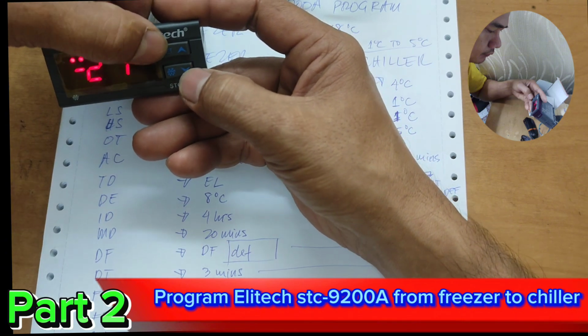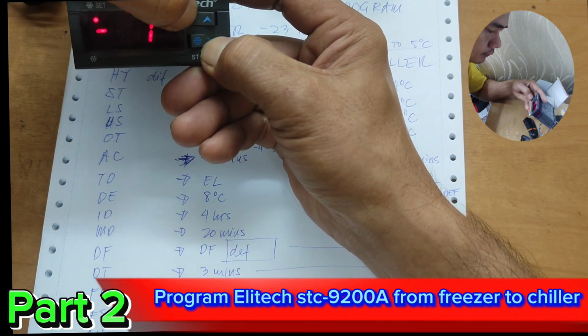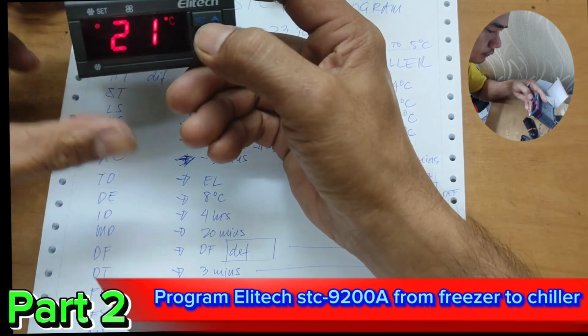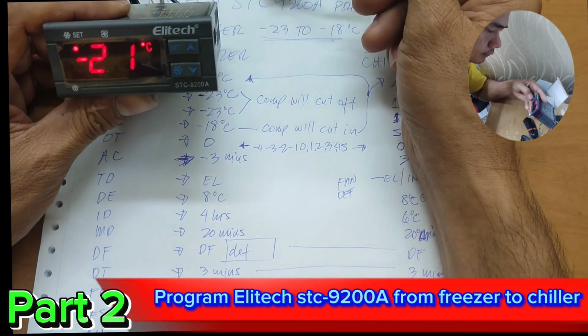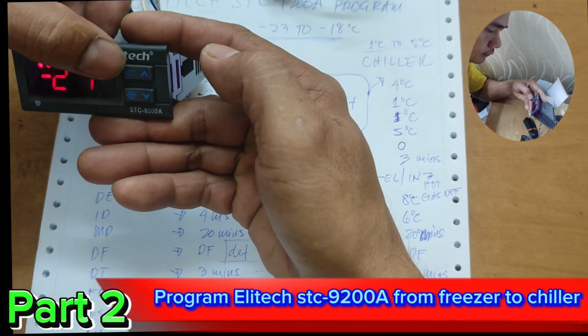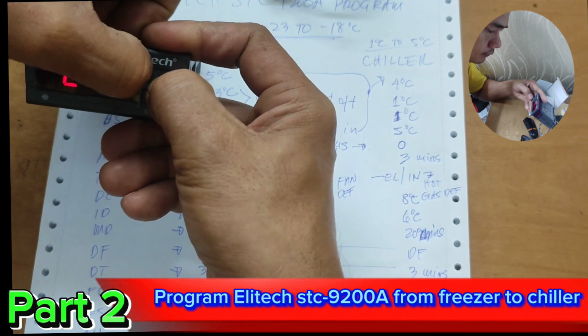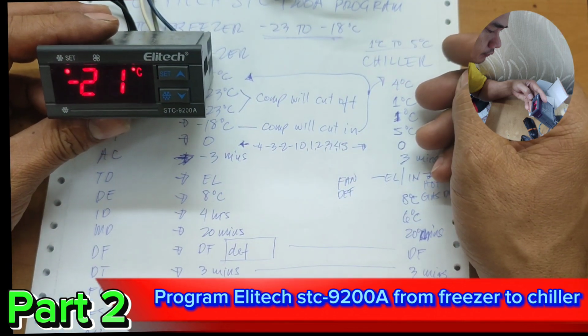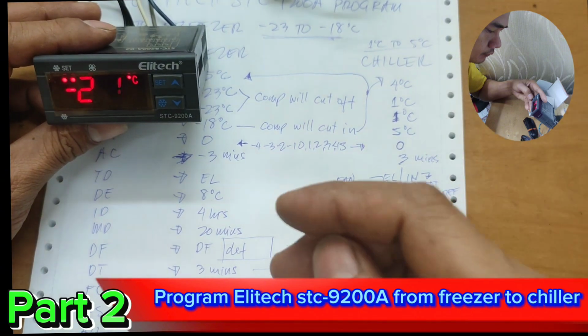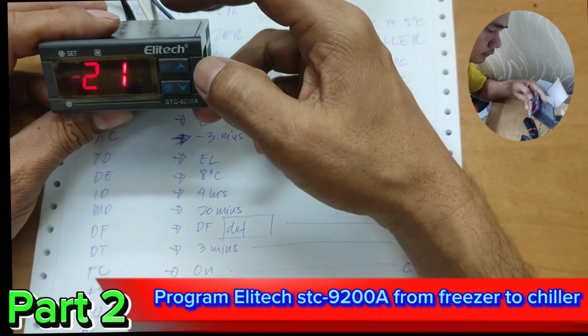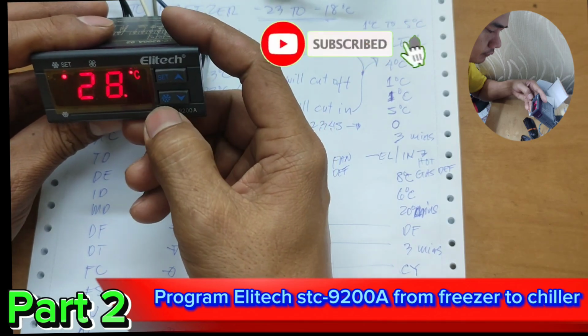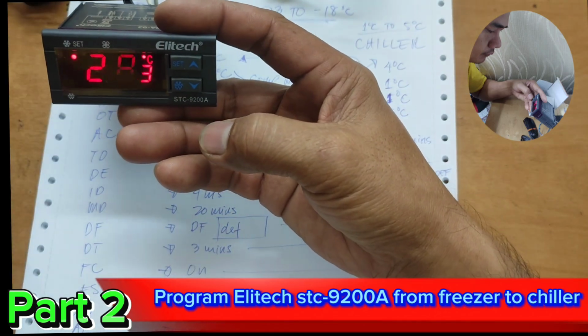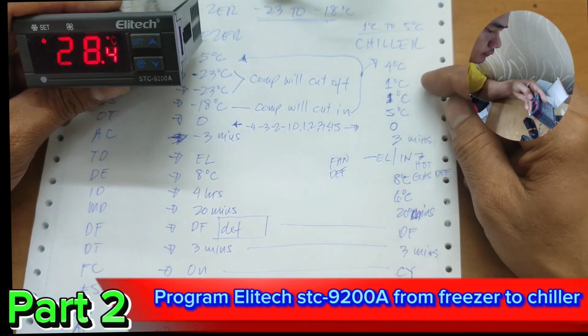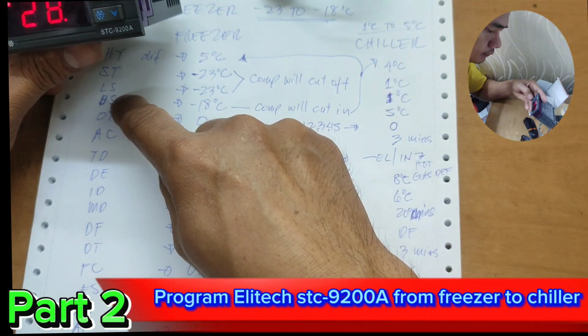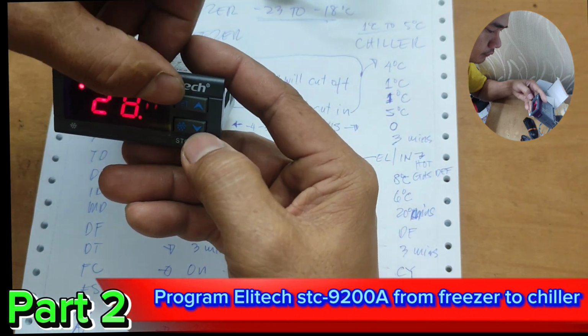Press set button here and arrow down button for 3 seconds, or just long press it. Okay, I cannot change it. Let's just wait, or let's press the set button and up button. Let's just wait. There. Now, we cannot change the set point because of the limit done by the LS and US. So, we're going to enter the programming by pressing the set button and arrow down button. Just long press it.